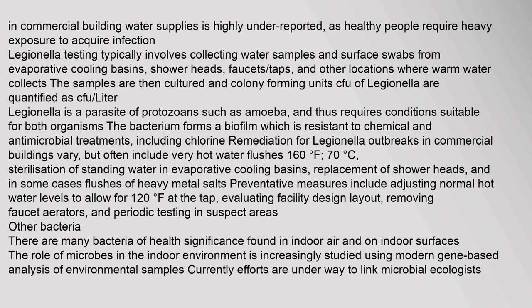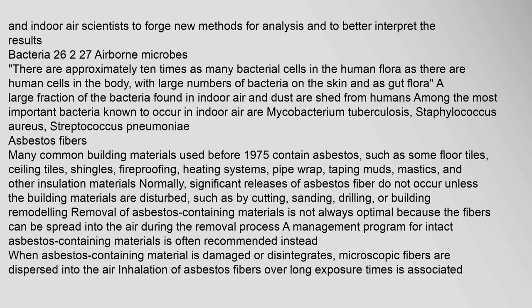The presence of Legionella in commercial building water supplies is highly underreported, as healthy people require heavy exposure to acquire infection. Legionella testing typically involves collecting water samples and surface swabs from evaporative cooling basins, showerheads, faucets, taps, and other locations where warm water collects. The samples are then cultured and colony-forming units (CFU) of Legionella are quantified. The bacterium forms a biofilm which is resistant to chemical and antimicrobial treatments, including chlorine. Remediation often includes very hot water flushes at 160°F.